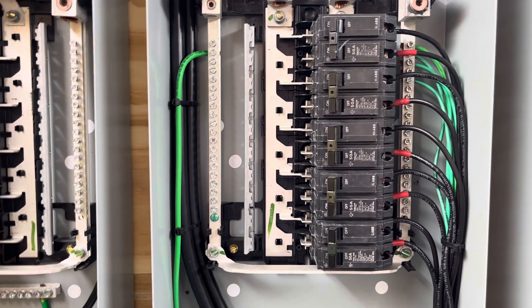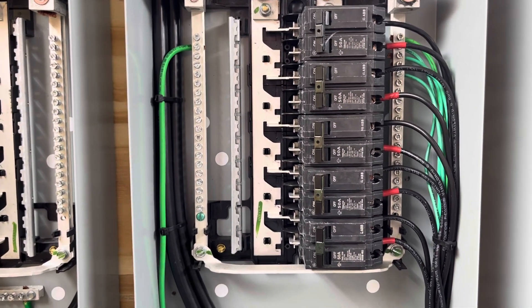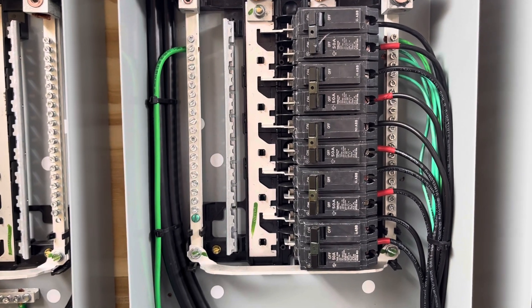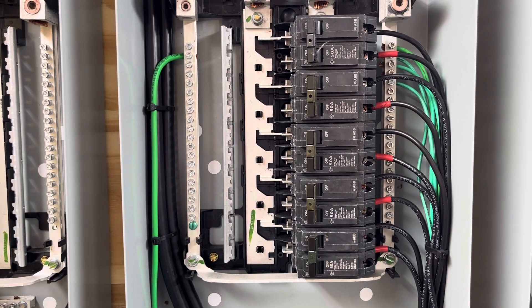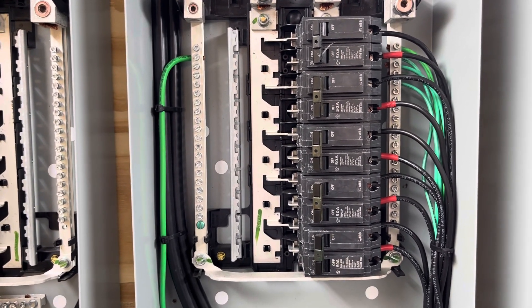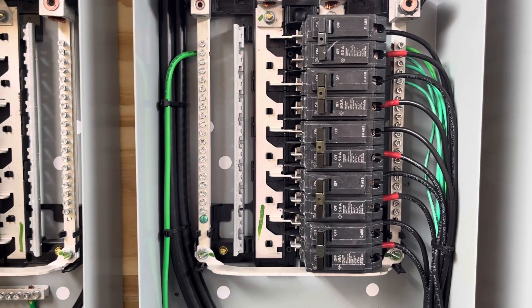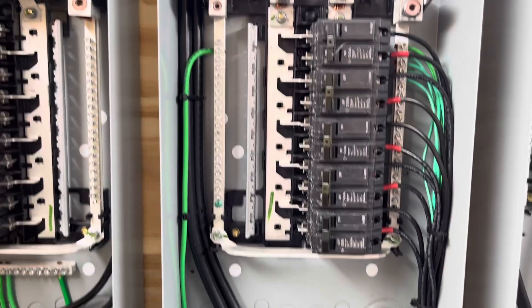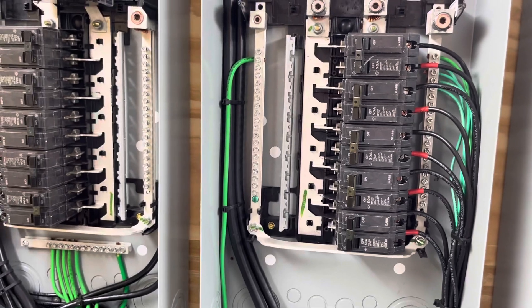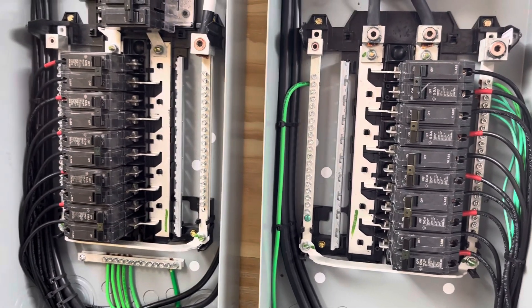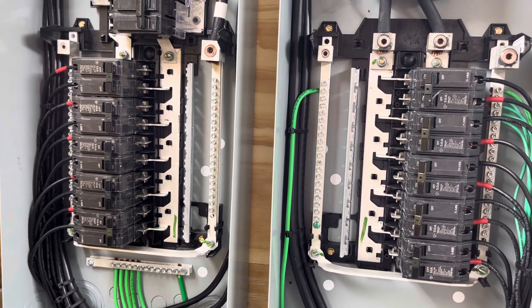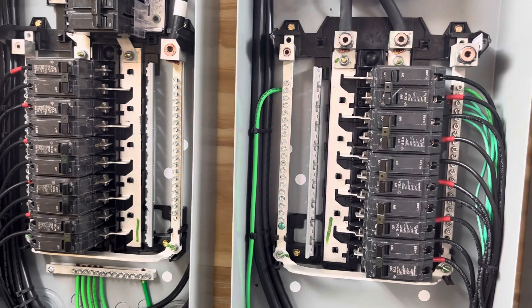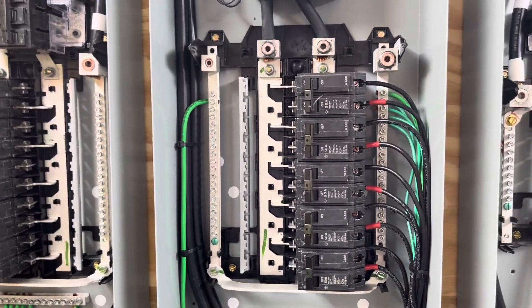So that's the reason these inverters are set up. They're not grid-tied inverters, meaning we cannot back feed the grid. We cannot back feed our meter or do any net metering with this system. It takes a grid input, but it does not produce a grid output.